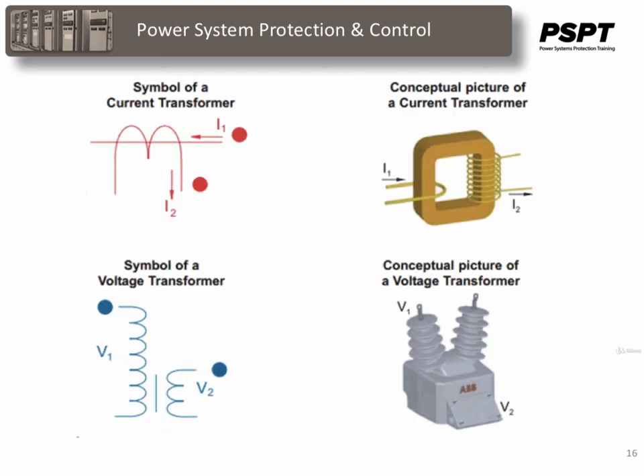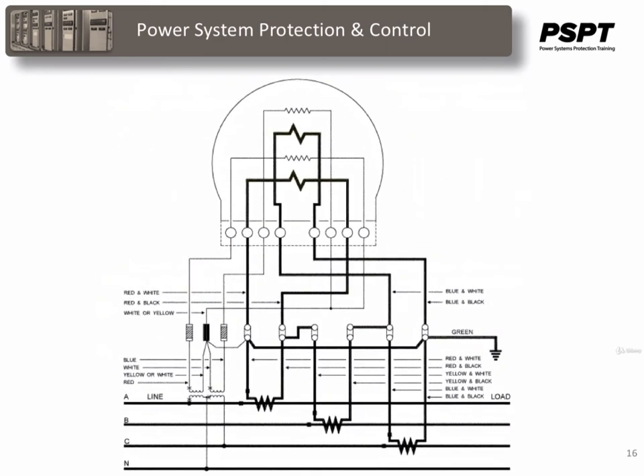On schematic drawings, PTs and CTs with their polarity markings may look something like this. This is an actual standard drawing using PTs and CTs with their polarity marks and connected to give the right measurements for a kilowatt-hour meter. You can see the PTs on the bottom left. The spot markings of the PT look like X's on the coils of the transformer, and in the case of the CTs, the spot markings look like square or rectangular boxes on the sides that are the marked sides of the CT.